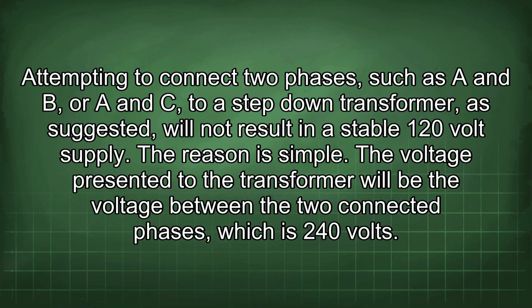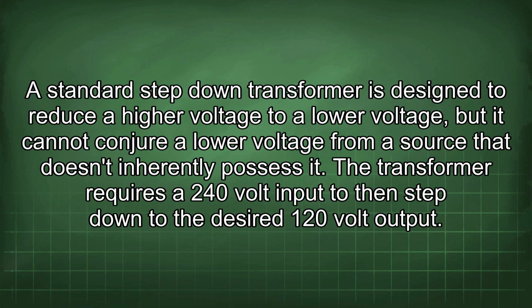The reason is simple. The voltage presented to the transformer will be the voltage between the two connected phases, which is 240 volts. A standard step-down transformer is designed to reduce a higher voltage to a lower voltage, but it cannot conjure a lower voltage from a source that doesn't inherently possess it. The transformer requires a 240 volt input to then step down to the desired 120 volt output.